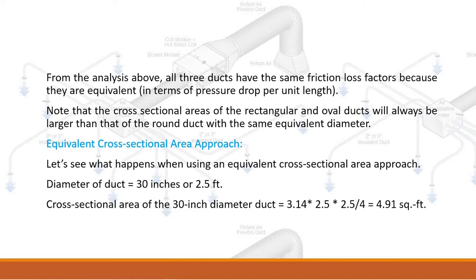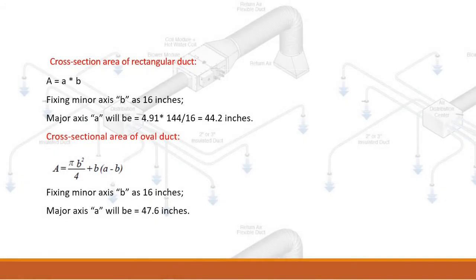Equivalent cross-sectional area approach. Using a 30-inch diameter duct (2.5 feet), the cross-sectional area equals π × 2.5² / 4 = 4.91 square feet. Fixing the minor axis B at 16 inches, the major axis A for the rectangular duct equals 4.91 × 144 / 16 = 44.2 inches. For the oval duct with minor axis B at 16 inches, the major axis A equals 47.6 inches.